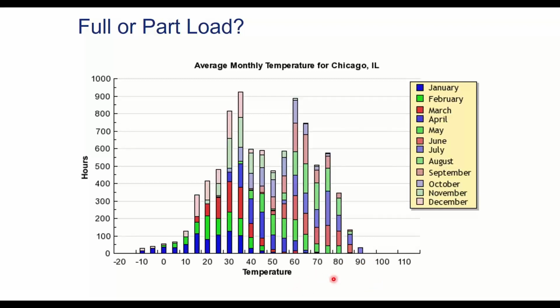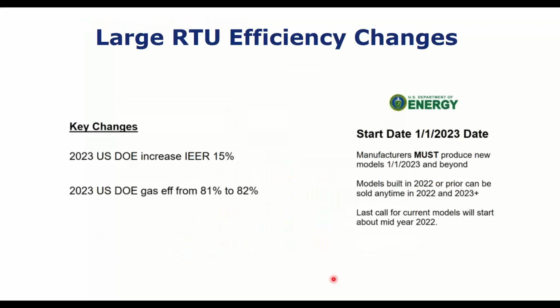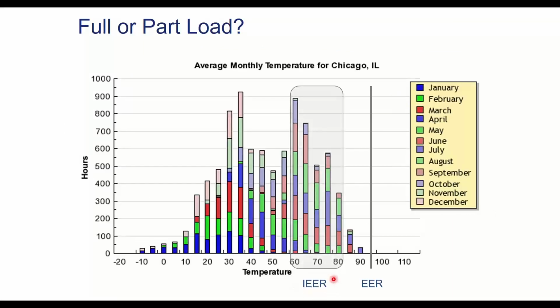And that's why this Department of Energy standard doesn't even talk about full load. EER, there's no minimum EER. There isn't. It's only IEER. That's all that matters, part load. You can be horrifically inefficient at full load, but it doesn't matter because it only happens 10 hours a year. Obviously, if you get some kind of process thing going on, that's different.